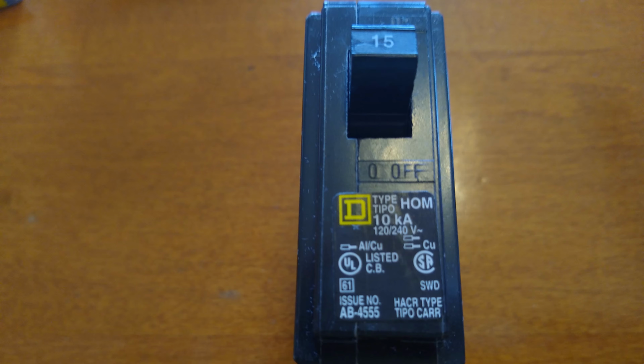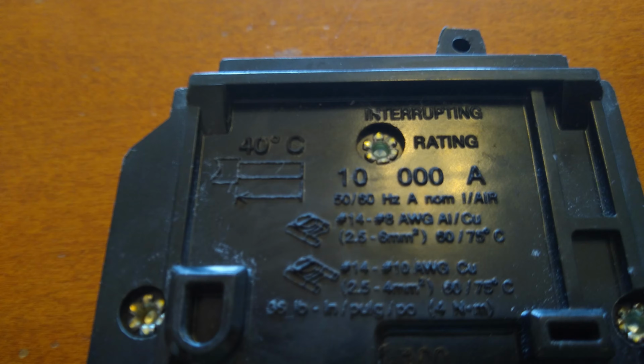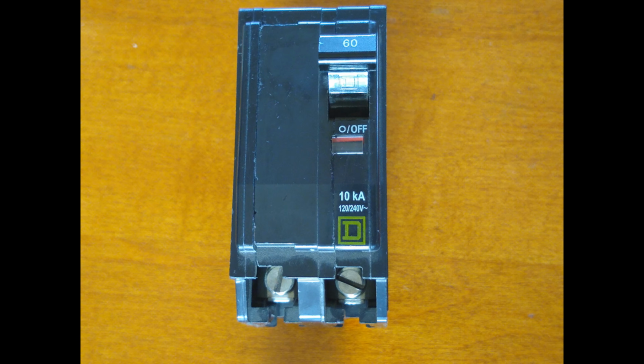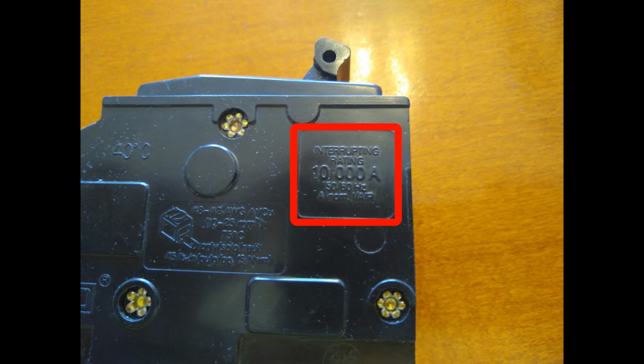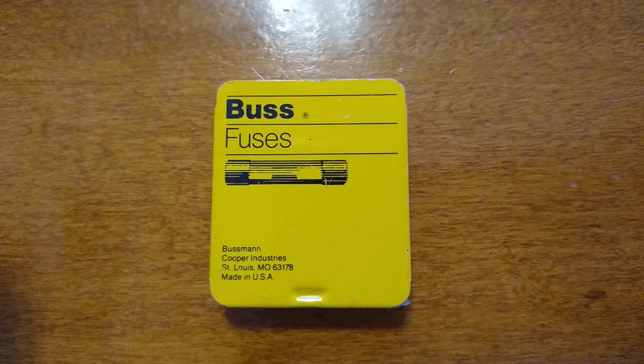So here's some examples. This is a Square D Homeline 15 amp circuit breaker. See where it indicates 10 kA? That's 10,000 amps. But we can also see the interrupting rating of 10,000 amps is molded right into the side of the case. Here's a 60 amp Square D QO circuit breaker. It also indicates 10 kA right on its face, and its interrupting rating of 10,000 amps is molded right into the case. And here's one of the classic Bussmann fuses I'm using for my project. Even these small 1/4 inch by 1.25 inch glass fuses, AGC 1/4, are rated to interrupt 10,000 amps at 125 volts AC.